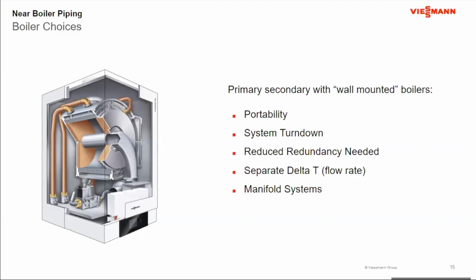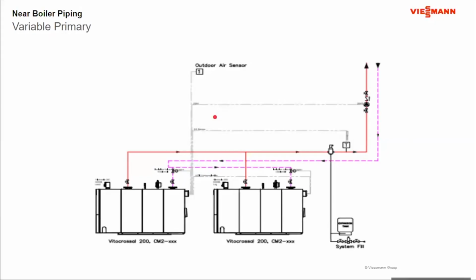So although this boiler is tied to specifically doing primary, secondary, there are other things that also make it very attractive, when I look at doing this versus possibly doing a different boiler in a variable primary install. Okay, so if we look at our different piping arrangements that are available, so we talked about the higher mass boilers doing variable primary. So here's variable primary.